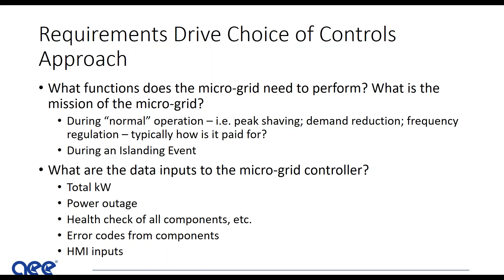Typically you have two, at least in the stuff I've been doing. Normal operation, maybe it's peak shaving. I've predetermined the peak shaving total KW, so I'm watching the KW, the value, slope, weather forecast, etc. You can turn the microgrid and power components on to drop the demand so you don't get hit with a demand charge. A lot of the ones we work with have ratchet charges, meaning if your peak demand hits 20 megawatts in July, that's your peak for the year, and you pay that rate whether you hit it again or not, for the year forward.